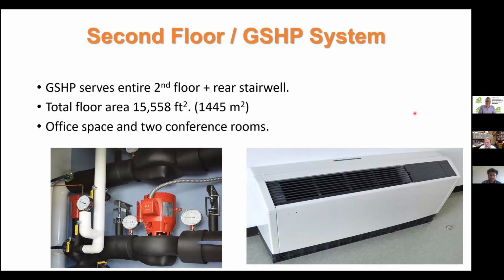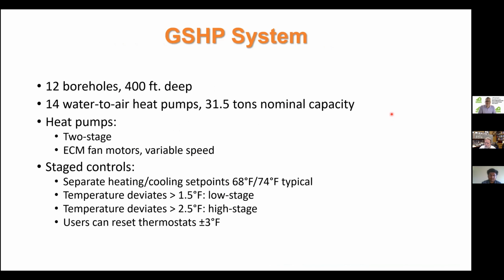So the ground source heat pump system, there's not so much to show because most of it's either underground or in the ceilings. I think there was one console unit in the stairwell, this unit here. There was a mechanical closet with a glass door on it. And this picture was taken through the glass door with 2 pumps and some pressure gauges and so on. But that's it for the mechanical room. There's no other room anywhere. So it served the entire second floor plus the rear stairwell, a little bit less floor area, mainly office space, and there's a couple of conference rooms. There were 12 boreholes, 400 feet deep, 14 water to air heat pumps with a total capacity of 31.5 tons.